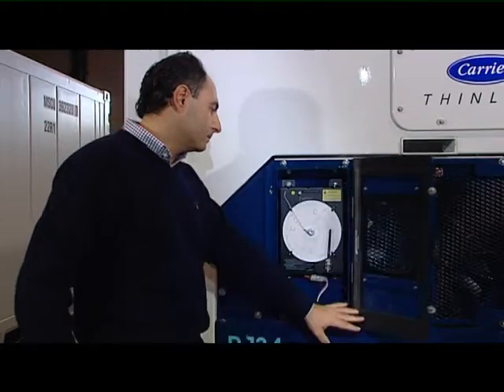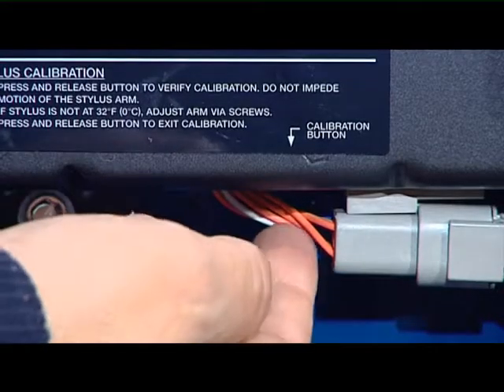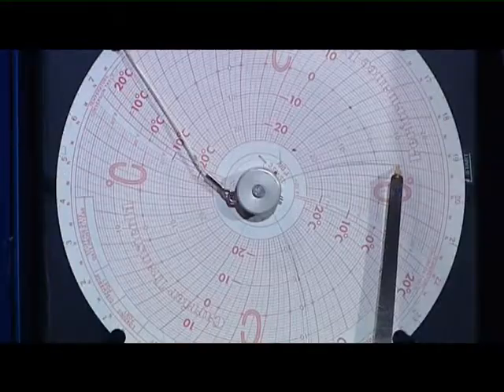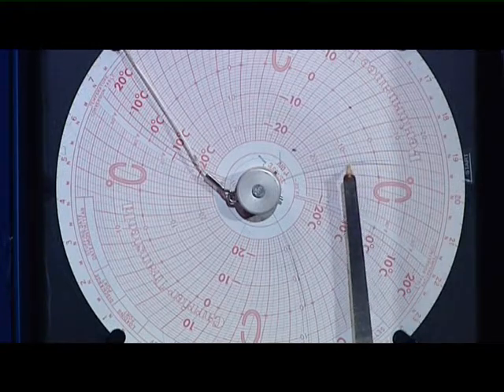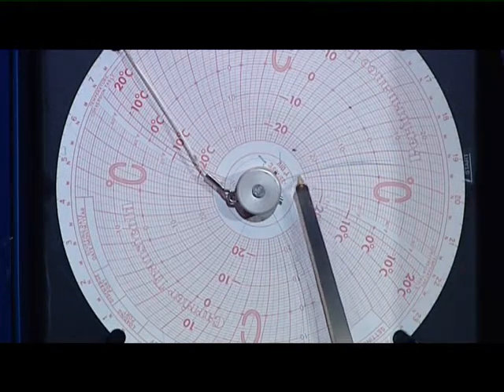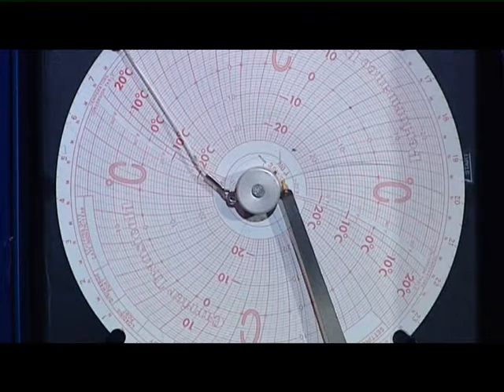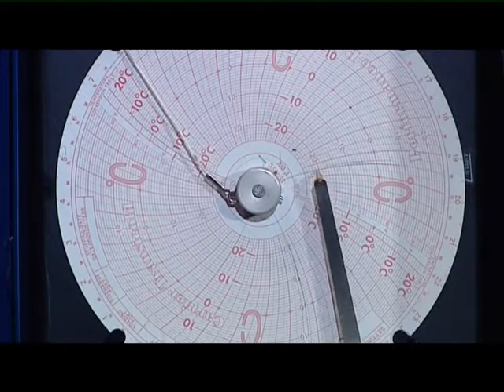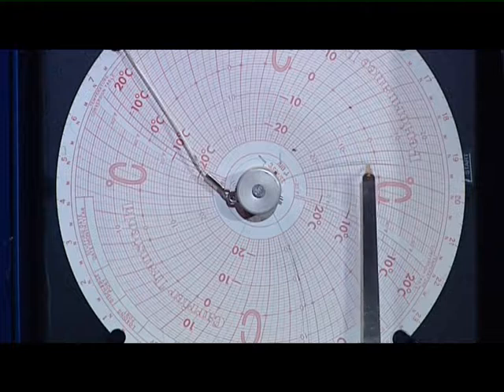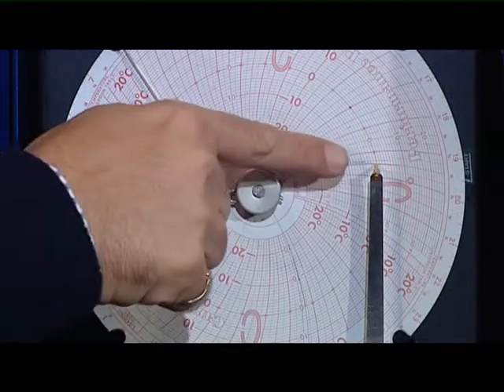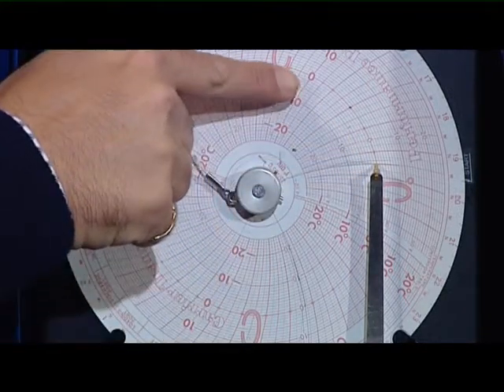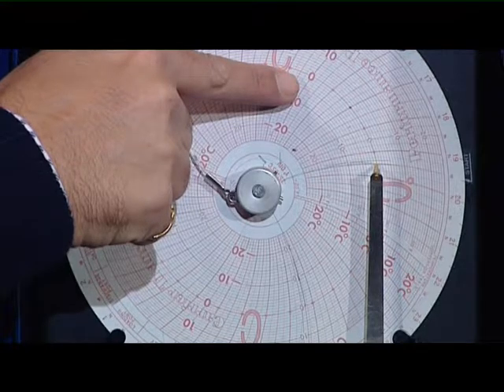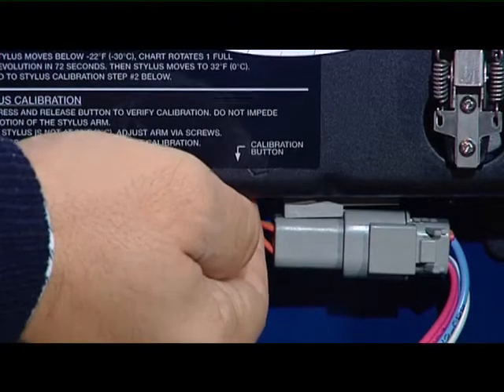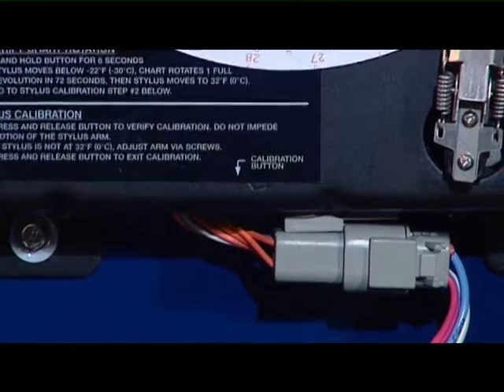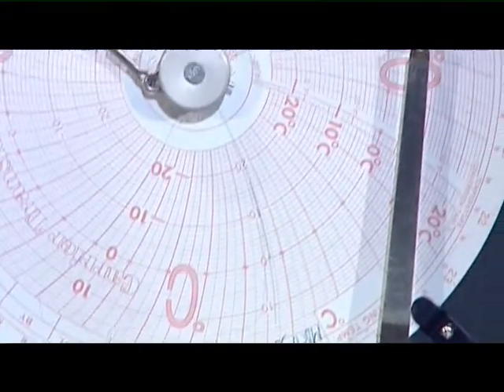It's possible to calibrate the electronic part low by pressing the calibration button on the bottom of the recorder. The pen will drive completely downscale and then move back to 0 degrees and stop. If the pen is exactly on 0 degrees, the recorder is in calibration. Press the calibration button once again and the pen will return to the correct temperature readings.